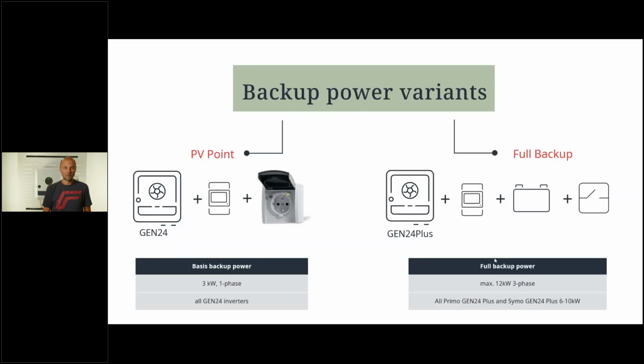If I start now with the first slide here, I'd like to give you a short overview about our backup variants. Basically, two solutions can be offered with the Gen 24 inverters. On the one hand side, there's the PV Point, basic backup power, which is supplied single phase, maximum 3 kilowatt with a specific socket. This can be used on all Gen 24 inverters. If it's a Primo, Symo, whatever power class, it doesn't even need to be a Plus inverter.